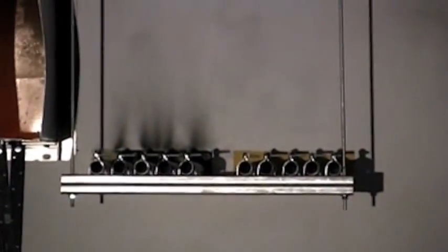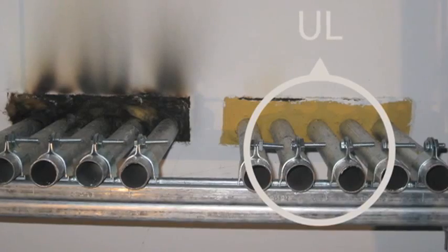The hole for the five conduits on the left uses glass fiber insulation, a material that does well in non-combustibility, but in the event of a fire softens and yields considerably. Its lack of suitability for this installation allows smoke and hot gases to pass rapidly through the fiberglass stuffed openings.